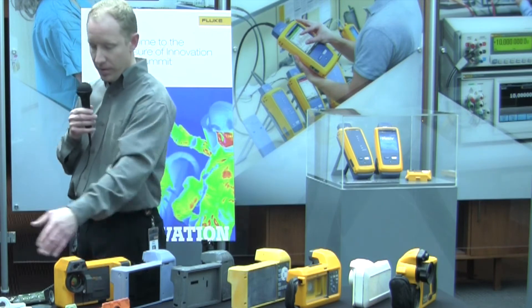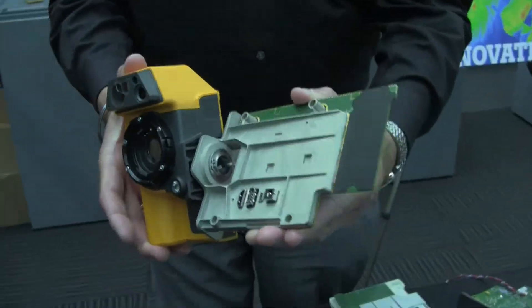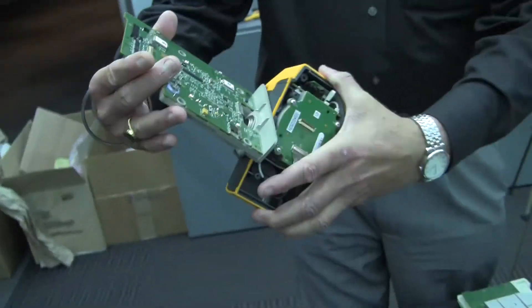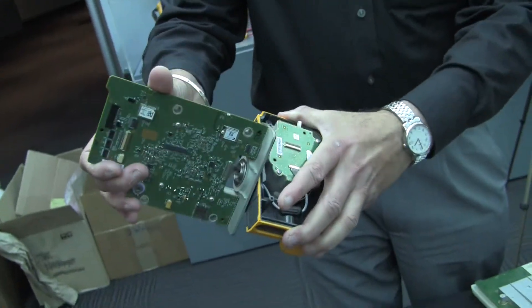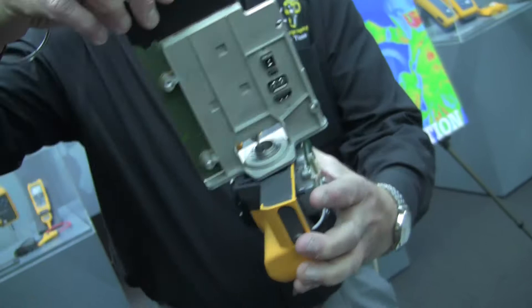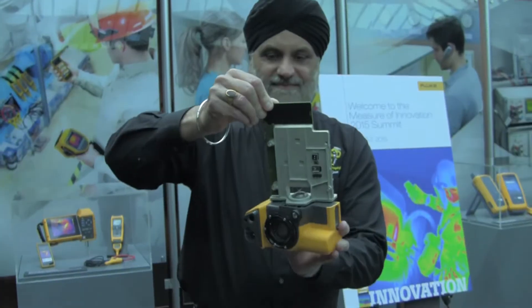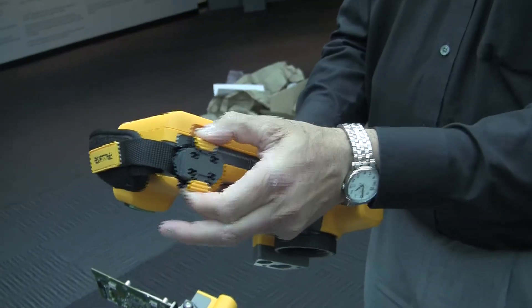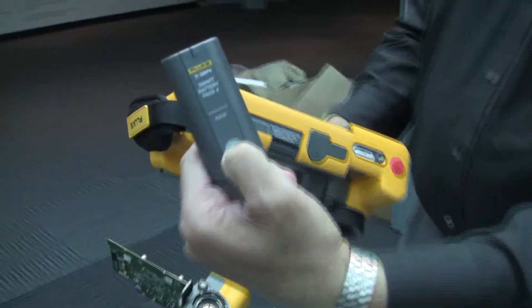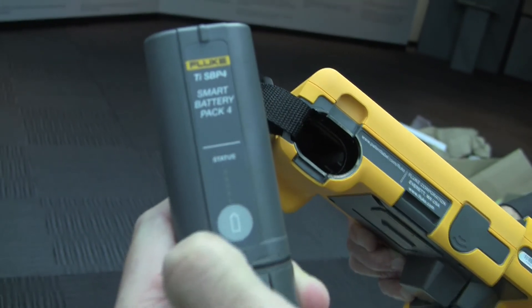We prototyped and did a lot of testing, and you can see some of that here. There's a metal chassis which integrates both the screen and the rotation joint, and that's one of the keys to the rugged product. Testing early and often, doing lifetime testing, integrating both the electrical design and the mechanical design early. Having a smooth feel on this joint and not having that create a problem with the electrical cable was a key aspect, but it took many iterations to do that.